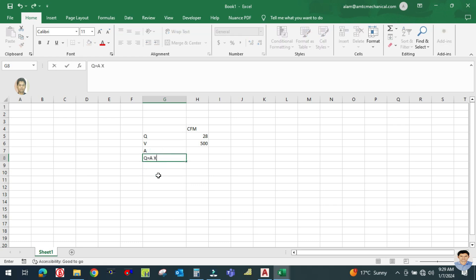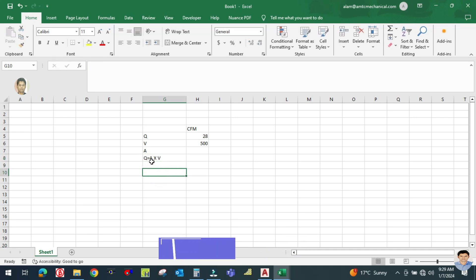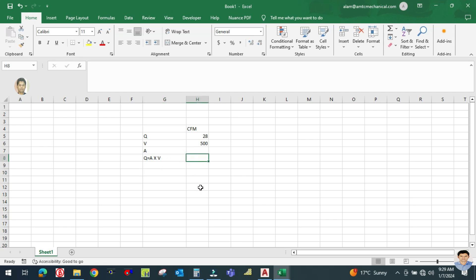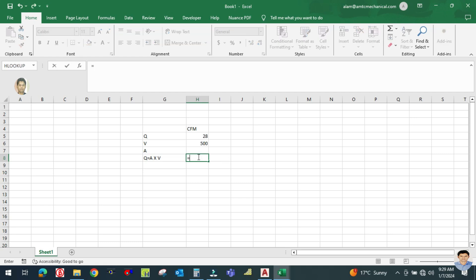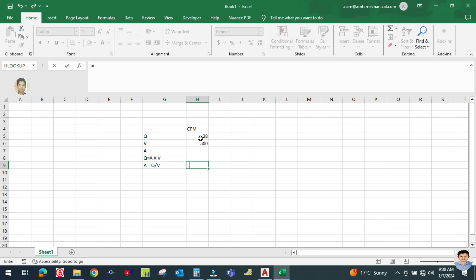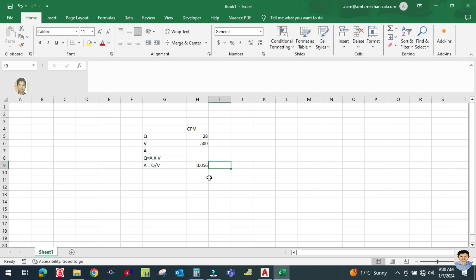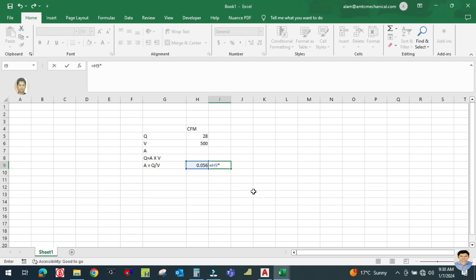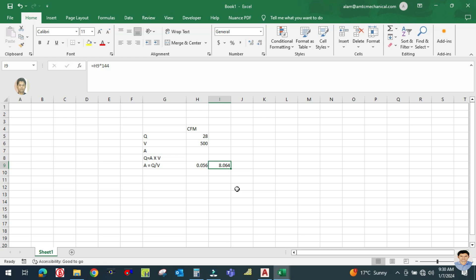The equation is: Q equals A multiplied by V, meaning flow rate equals area multiplied by velocity. Rearranging, A equals Q divided by V. With Q equal to 28 CFM divided by a velocity of 500, we get 0.056 square feet. Converting to square inches by multiplying by 144 gives approximately 8 square inches.